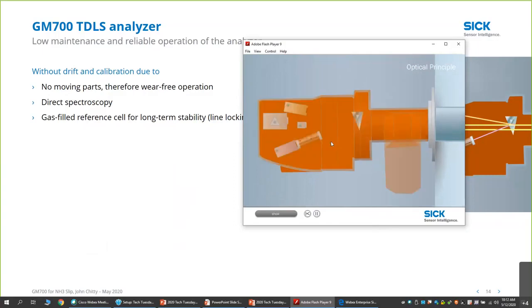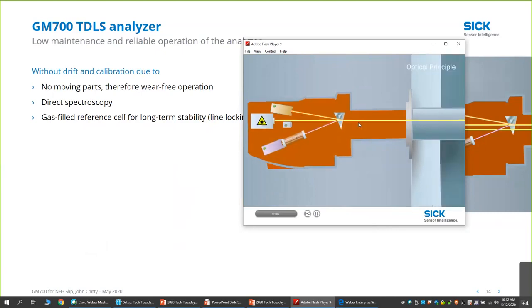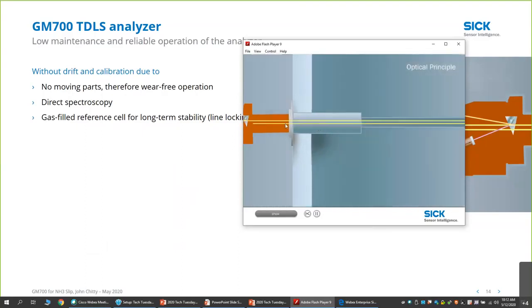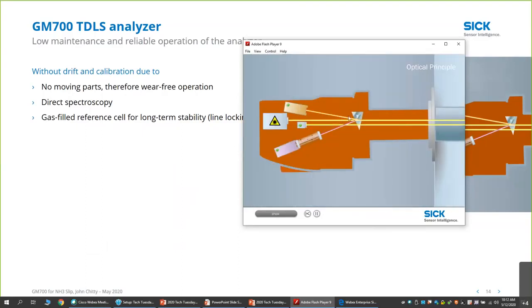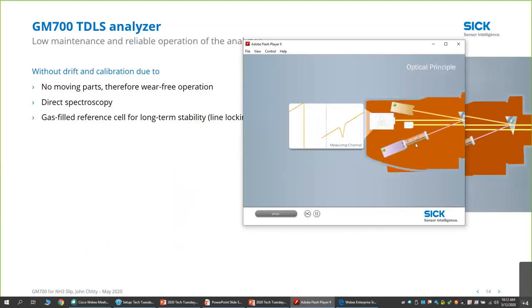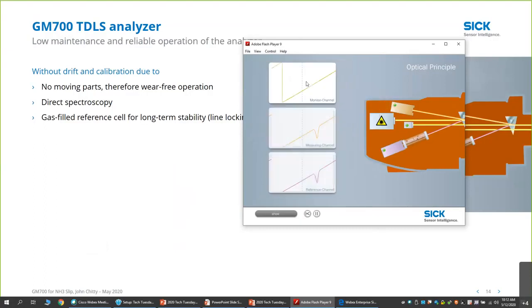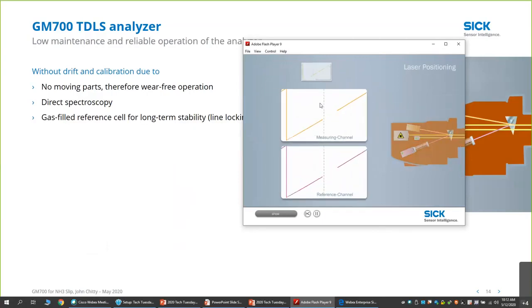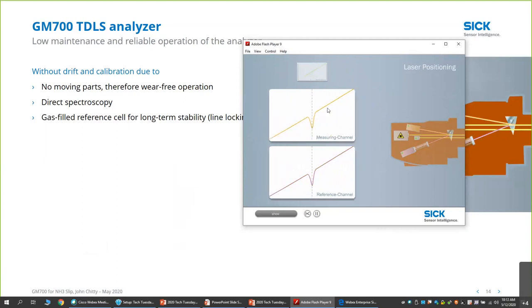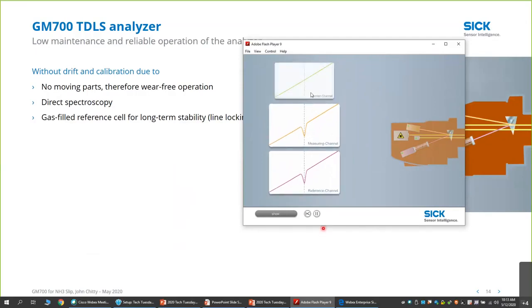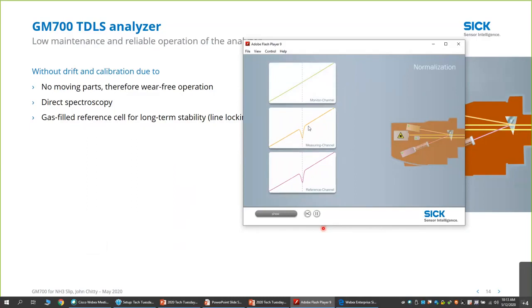So inside of the analyzer, we have the laser. It shoots the laser beam and hits a beam splitter. It goes out to the reflector and bounces back and hits the detector. Now the beam splitter branches off to a monitor channel and a reference channel. So in one measurement, we're really doing 3 measurements. We're measuring the actual signal, a reference, and the monitor channel gives us a baseline. So we're able to take those 3 measurements and do a normalization of the curve. We're comparing the reference and the measuring. That gets compared to the baseline, and we're able to normalize this into a flat curve.